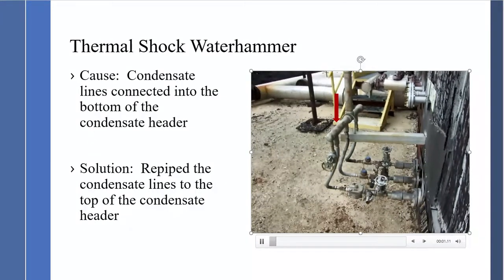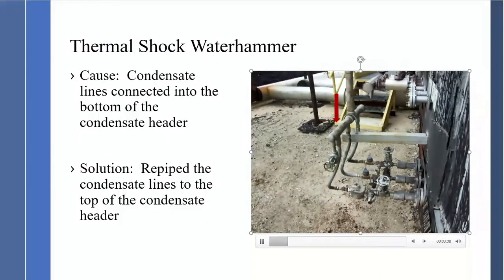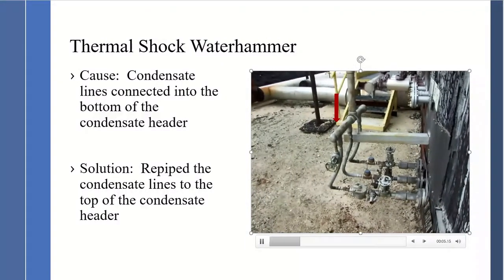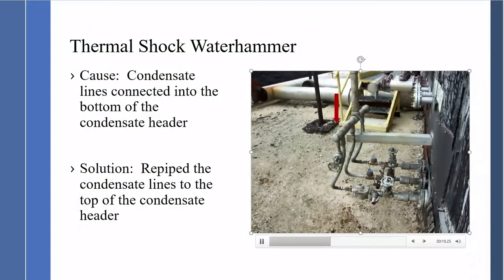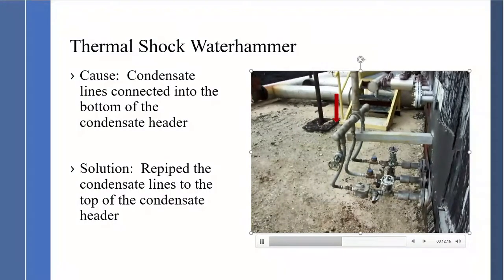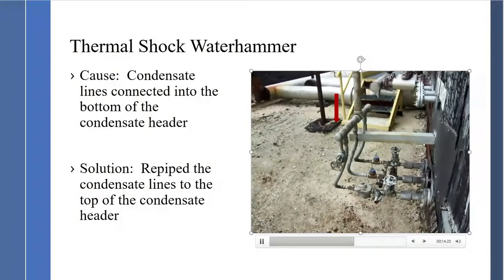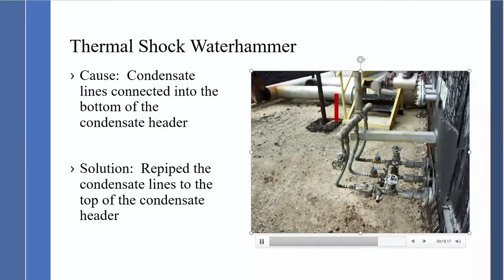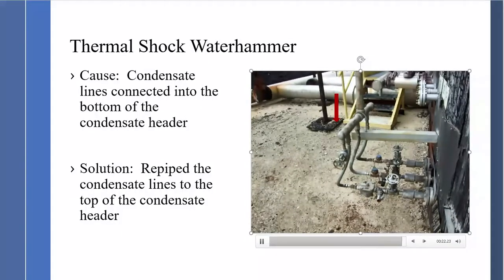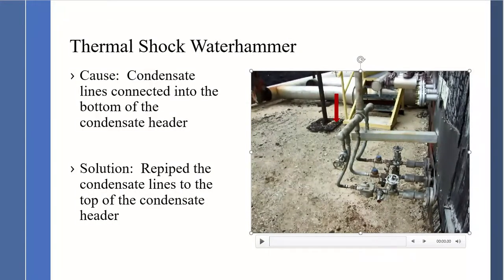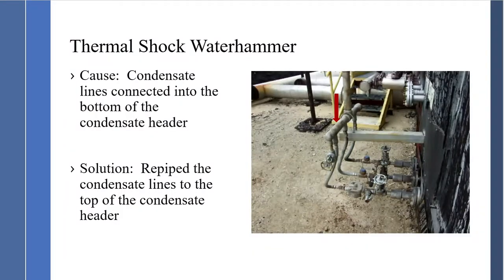Here is another video where the connection is into the bottom of the condensate header. Again, the solution is to re-pipe into the top of the condensate header and the water hammer will go away.